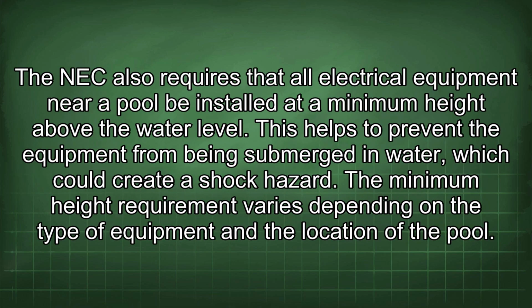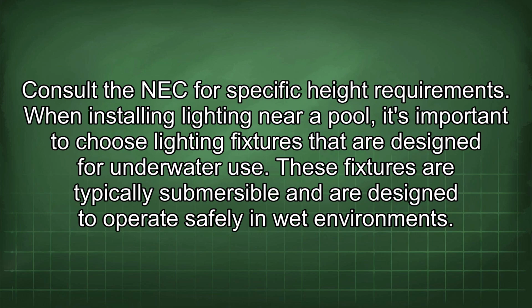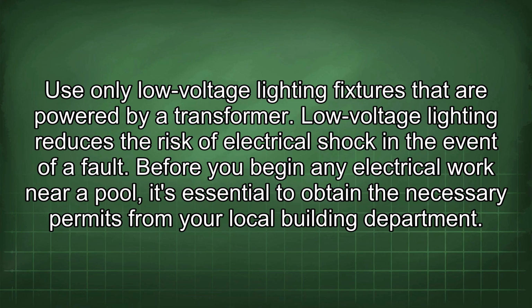The NEC also requires that all electrical equipment near a pool be installed at a minimum height above the water level. This helps to prevent the equipment from being submerged in water, which could create a shock hazard. The minimum height requirement varies depending on the type of equipment and the location of the pool. Consult the NEC for specific height requirements. When installing lighting near a pool, choose lighting fixtures that are designed for underwater use. These fixtures are typically submersible and are designed to operate safely in wet environments. Use only low-voltage lighting fixtures that are powered by a transformer. Low-voltage lighting reduces the risk of electrical shock in the event of a fault.